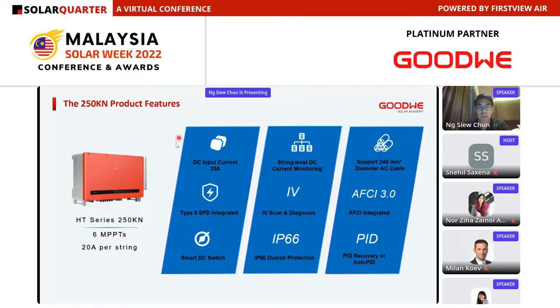So we do support up to DC input current of 20 amp, and integrated is also our Type 2 SPD for DC and AC side. So you do not need to put any combiner box also for protection. And this works with a very unique technology that we also improved on our products, a smart DC switch. What is so smart about this DC switch is basically it will automatically trip when there is overcurrent. And when the overcurrent is resolved and the error is acknowledged, it will automatically connect back.